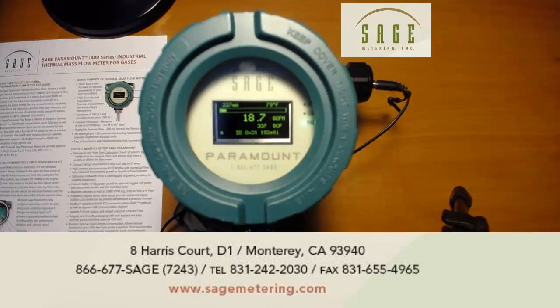Regarding the SageCom software that comes with the meter, it not only allows you to do the in situ calibration verification, but it also lets you reconfigure the meter, whether it be changing full scale, changing engineering units from SCFM to SCFH, and there's many other features, including changing the gas mix if desired.